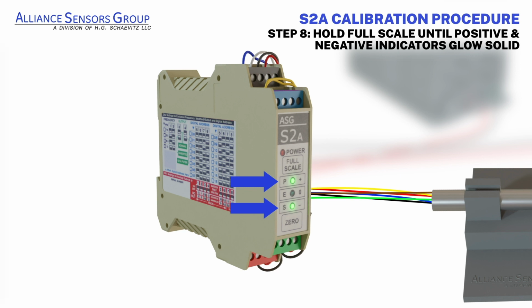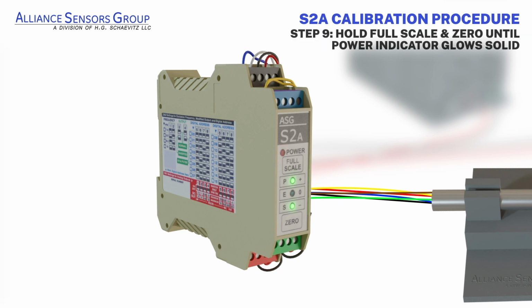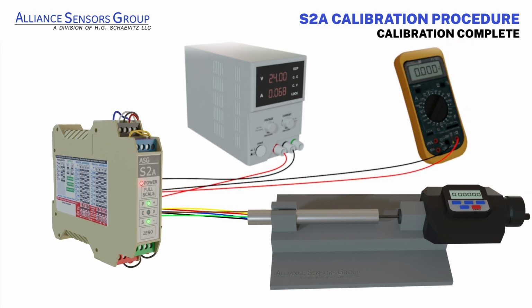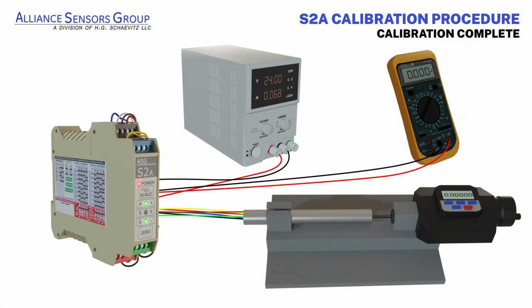Finally, to return the S2A to its run mode, press both the full scale and 0 buttons simultaneously until the red power indicator glows solid. The measuring system is now ready for operation. We can now observe that the DC voltmeter displays an output voltage of 0 volts DC from the S2A with the LVDT's core at the 0-inch position and 10 volts DC when the LVDT's core is at the 1-inch position.